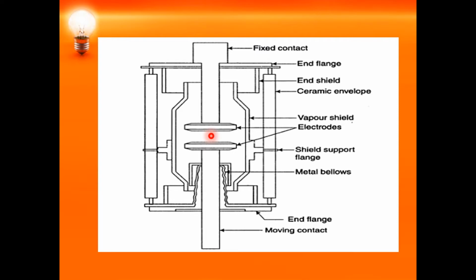The disadvantages of the vacuum circuit breaker: obviously it will have some disadvantages. It needs very high technology for the production of vacuum interrupters, and it needs an additional surge suppressor for the interruption of low magnetizing currents, because magnetizing currents shouldn't be treated as a fault, right? And there might be loss of vacuum due to transit damage. So these are some of the disadvantages of the vacuum circuit breaker.